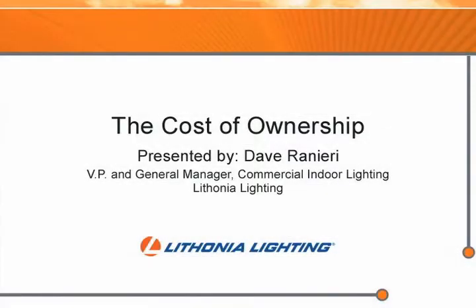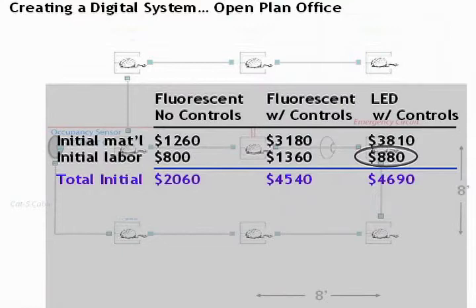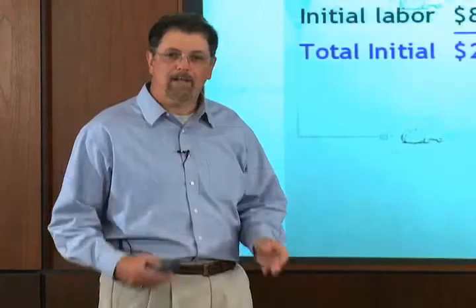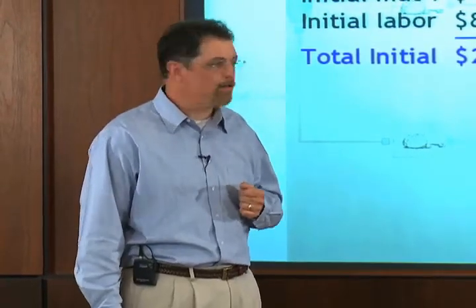Most commercial applications today do require some type of controls. In this case, we have an open plan office with nine luminaires. And if you install the system without any type of control, a conventional fluorescent system without any control, you can see that the initial cost is going to be quite a bit lower. But if you do compare the LED system with controls with a comparable fluorescent system that also uses dimming control, you can see that the initial cost difference is very close. And that's mainly due to the reduced cost of the equipment and the labor to install the controls initially.